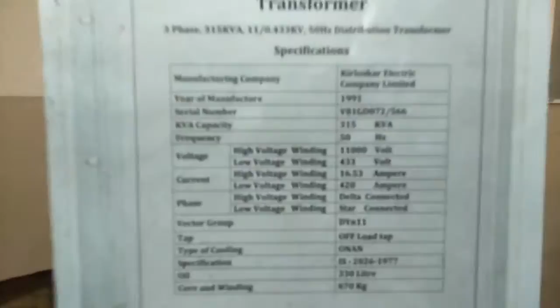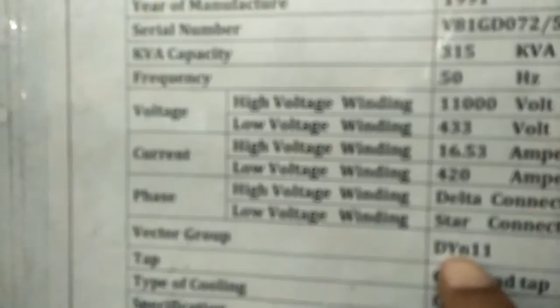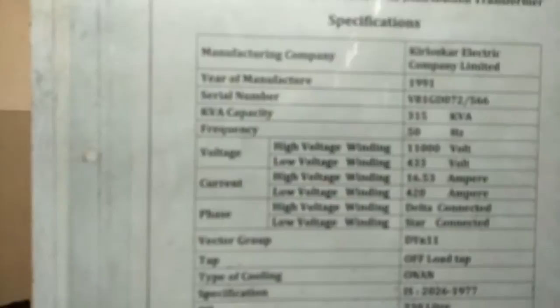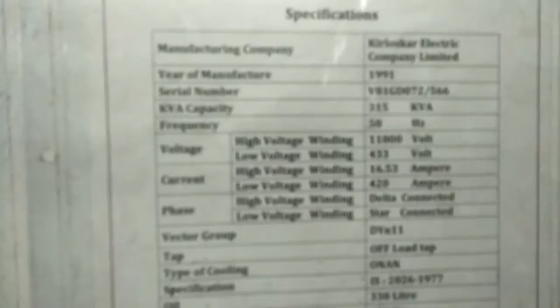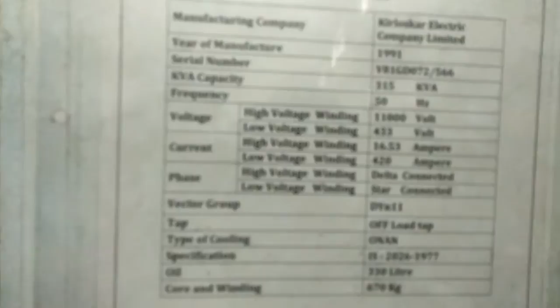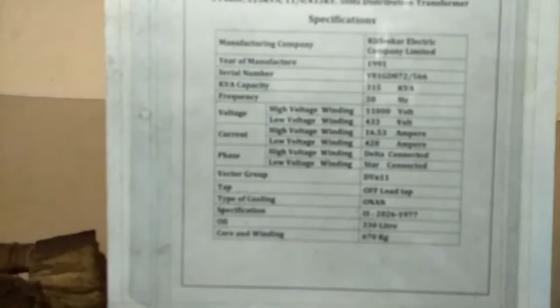This is the nameplate of the transformer, a three-phase 315 kVA transformer, and the vector group is DYN11. D stands for the primary winding being delta connected, Y means the secondary winding is star connected, and 11 means the secondary voltage is leading. On the clock, the angle between 12 and 11 is 30 degrees, meaning the LV voltage leads by 30 degrees with reference to the primary voltage, in the vector group notation which we already covered in our theory.